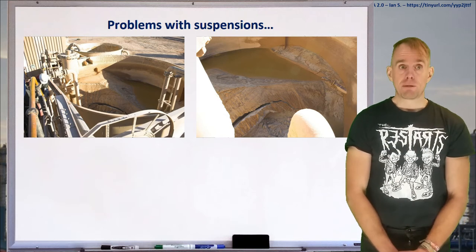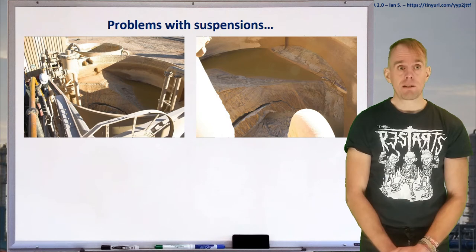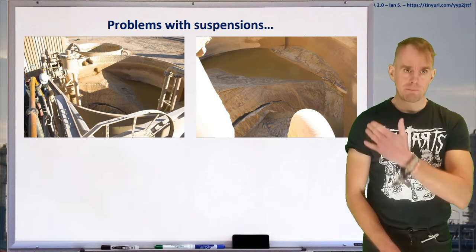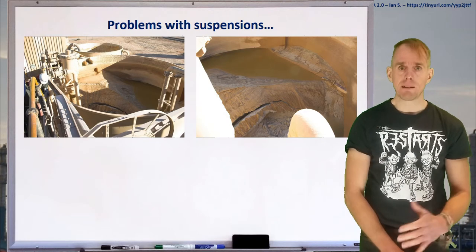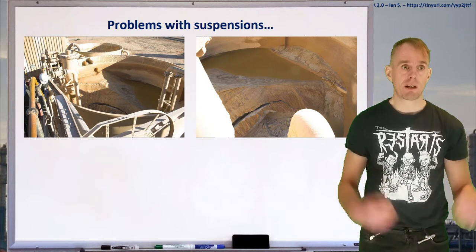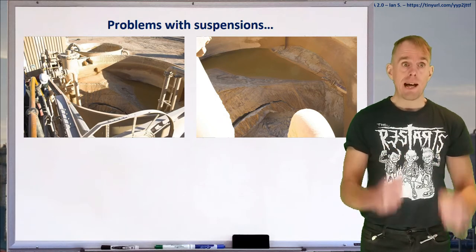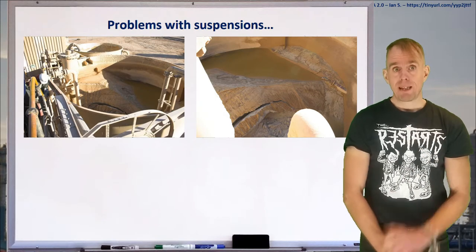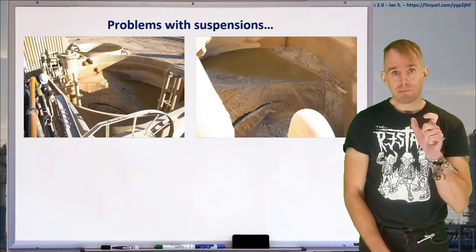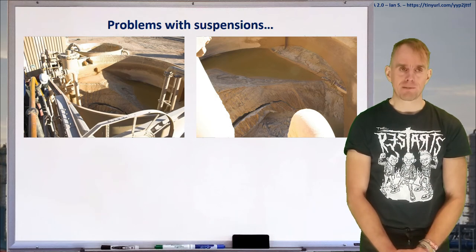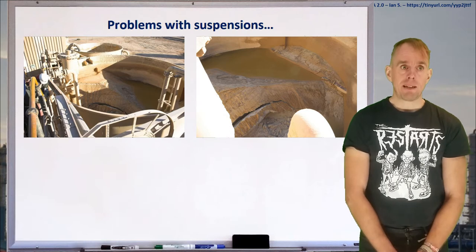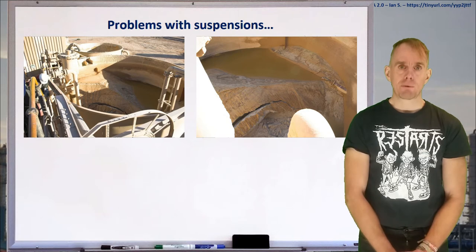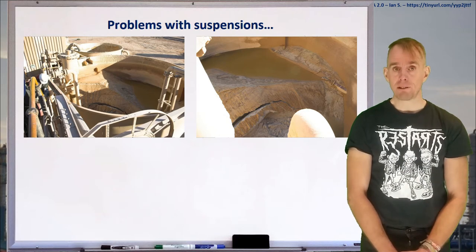So the way in which you solve this isn't pretty. You've got a couple of options. Either you get somebody into that tank with appropriate safety gear on. Remember that these solid areas have a consistency a little bit like quicksand. So you've got harnesses on, the poor person who's got to go in there, and a means of getting them out quickly. And you send them in with a shovel. Would you want to do that? If you don't want to do that, don't make somebody else do that. So design the thing properly in the first place. The other way you can deal with this problem is to get a backhoe loader in, and start digging the tank out. And that was tried. But unfortunately somebody nearly put the backhoe through the side of the tank, which nearly wrote the tank off.